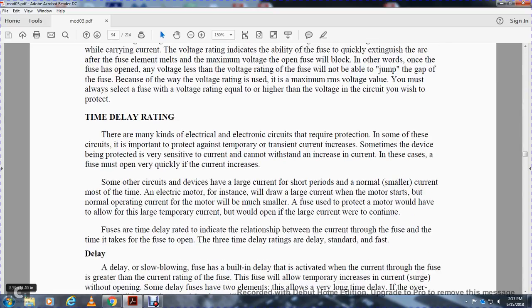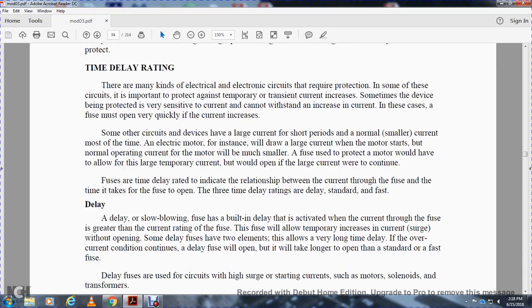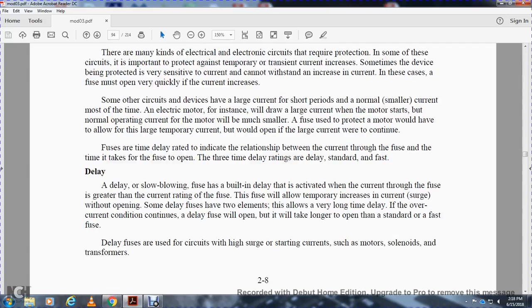Time delay ratings: electrical and electronic circuits may require protection from temporary transient current increases. Some devices being protected are very sensitive to current and cannot withstand even a momentary increase in current. In that case, the fuse must open very quickly when current increases. Some other circuit devices have large currents for a short period but normal smaller current most of the time. Electrical motors, for instance, draw a larger current when starting, but the normal operating current of the motor will be much smaller. The fuse used to protect the motor must allow the large temporary starting current but open if the large current were to continue. Fuses are time-delay rated to indicate the relationship between the current through a fuse and the time it takes the fuse to open. The three time-delay ratings are delay, standard, and fast.